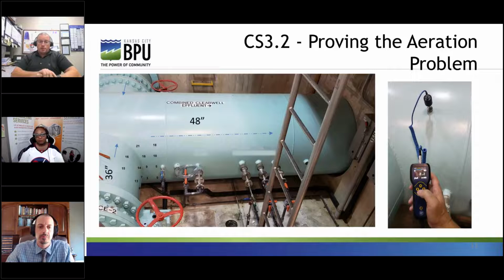For years, it was assumed the error in the sample line was due to oxygen concentration in the cold water, but we were unable to see through the pipes, so we just didn't know for sure. We'd really grown quite tired of the problems and wanted to get to the cause of it. We had recently acquired an SDT 340 and an SDT Ultra Checker for various condition monitoring uses around the plant. The 340 had been sent off for its annual calibration, but we still had the Ultra Checker and decided to take some structure-borne readings around the pipe.